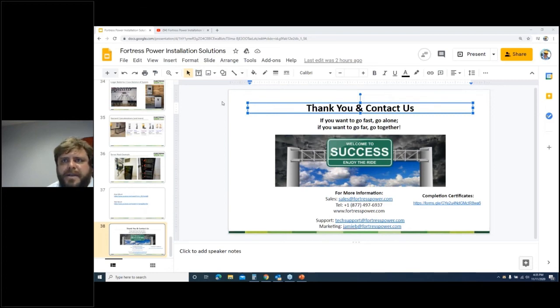Have we tested Fortress batteries in hot and humid climate conditions? What would be the impact of temperature on battery performance? Most specifically, we are concerned with cold temperatures rather than hot temperatures. If you're in an environment that regularly gets down to below freezing, it is best to put a heating element that only turns on during those times wherever you're keeping the battery to keep it warm. And that can sound like a daunting task. It might be, if your batteries are being kept in the garage, just building a little box for your batteries, running an AC circuit, and putting a very small thermostat heater in that battery box is all you need to do. When you're mounting the batteries outdoors in a cabinet, there are DIN rail mounted heaters you can buy.